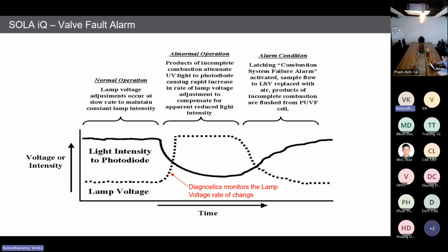So now the UV lamp is getting high voltage from the electronic circuit. The voltage changes very rapidly, meaning 30 volts per second is increasing, and our software will automatically detect it as a valve fault alarm. Normal voltage increasing or decreasing is maybe 1 to 5 volts, which is a normal condition. But in an abnormal condition, the voltage can vary 30 volts per second. With this abnormal condition, the software will detect some problem with the injection or with the process sample, so it will pop up the valve fault alarm.